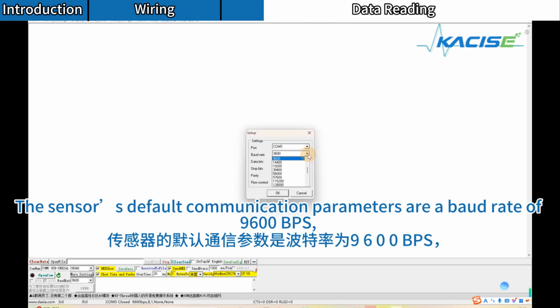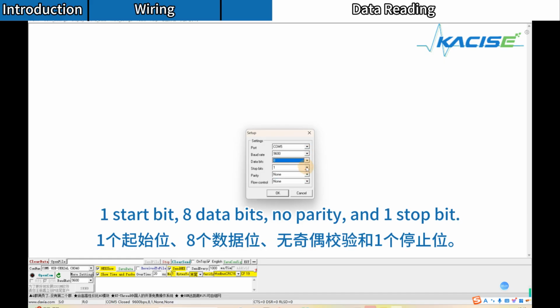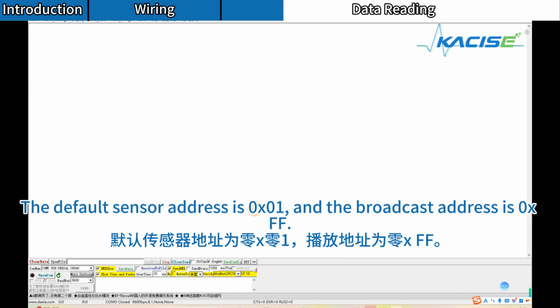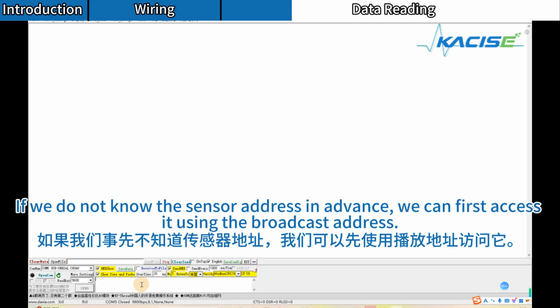The sensor's default communication parameters are a baud rate of 9600 bps, 1 start bit, 8 data bits, no parity, and 1 stop bit. The default sensor address is 0x01, and the broadcast address is 0xFF. If we do not know the sensor address in advance, we can first access it using the broadcast address.